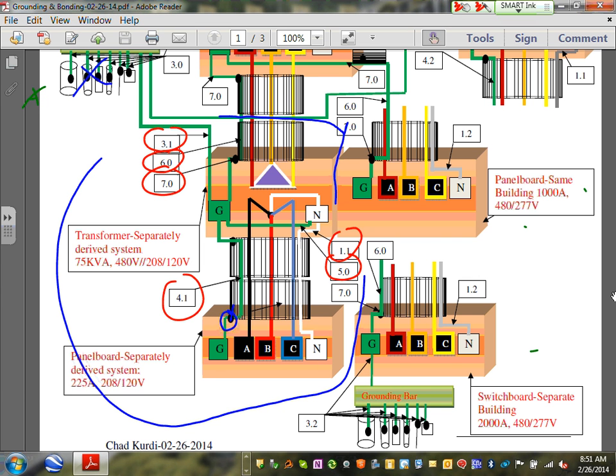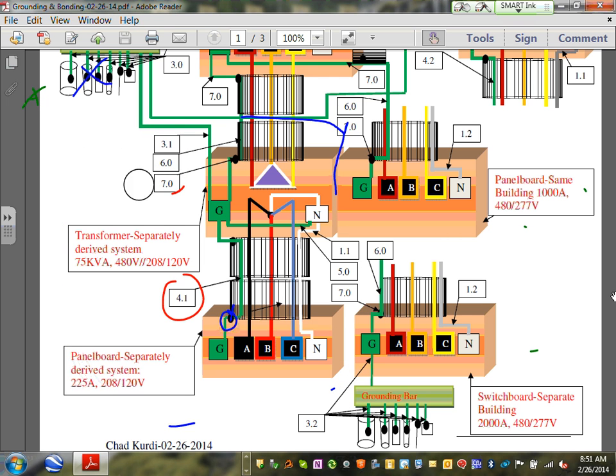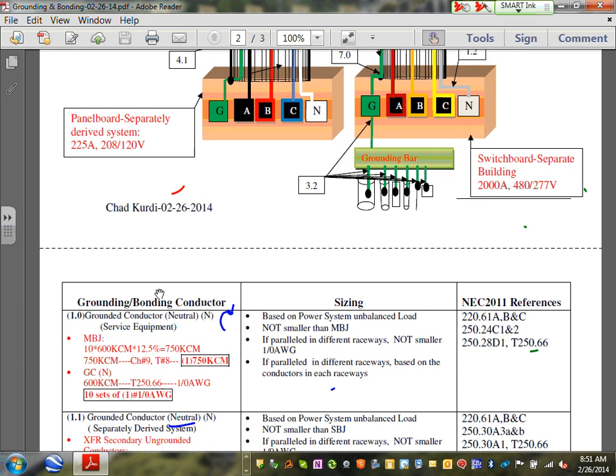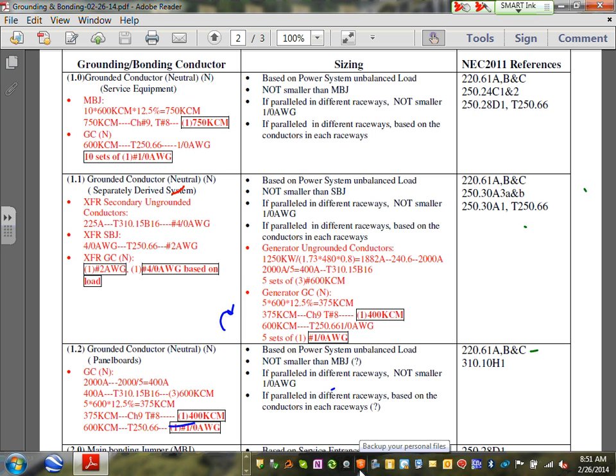Okay, so let's go, guys, size it, shall we? I'm going to size these 1, 2, 3, 4, 5, 6 things for that panel. Let's start with 1.1. Can you guys see that? I will start with 1.1, gentlemen, and walk my way through it. So here's my 1.1. 1.1 is a neutral. Here's 1.1, Adam. Remember, it's a neutral. For the transformer, I'm going to focus on the grounded conductor, the term that code uses, which is a neutral, at the transformer.